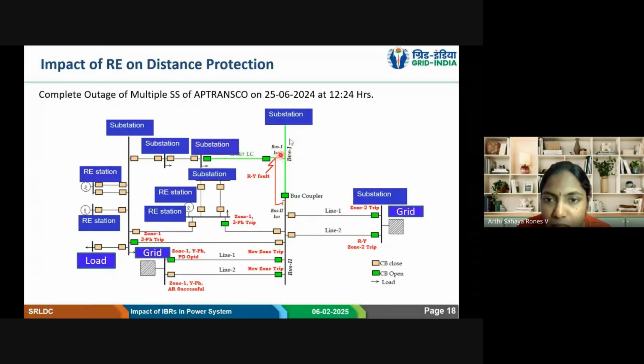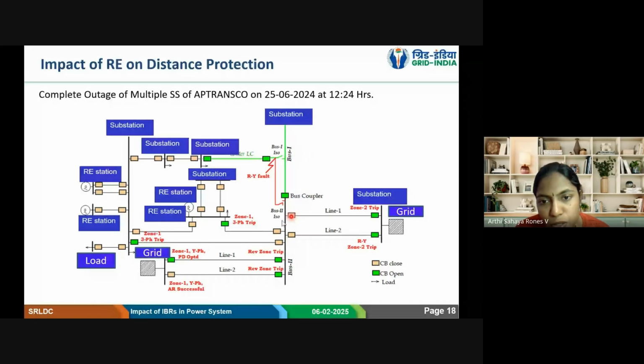And the fault was in the grid connected substation, a bus fault. So when this bus fault happens, ideally the bus bar protection should operate and clear this bus section, and all other elements connected to the other bus should stay connected to the grid. But what happened, the bus bar protection didn't operate. So because of that, the fault was cleared by the remote end. The remote end, for a bus fault, should sense it in zone 2. But we are seeing the RE station and the two RE stations sense the fault in zone 1. That means zone 1 overreach happened.